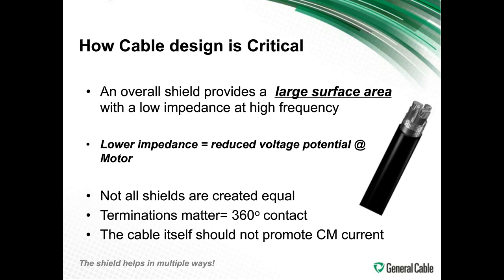And a braided shield can provide that because not all shields are created equal. Terminations, and the way that both ends are terminated with 360-degree contact of the shield, are very important. You want to make sure the cable itself is not promoting the common mode current. So in many ways, that shield is very effective to your whole system.